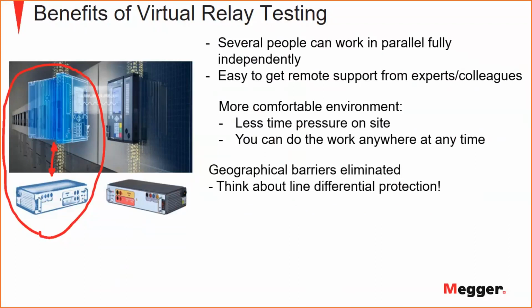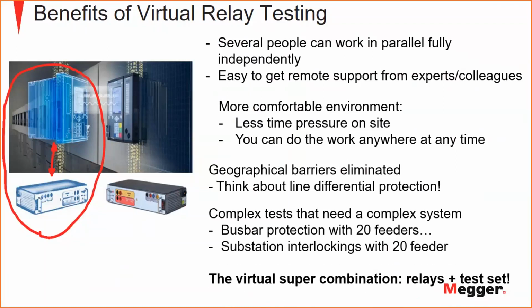Think that you can have two digital twins connected, and now I'm talking for Siemens, so I apologize if I say something wrong, but I believe it is possible to have two line differential protection relays, connected to the digital twins, connected to the real multiplexers into a communication channel. I guess, I'm not promising that. Anyway, I know you can connect these two relays together in the virtual world and test the line differential protection without doing the test we talked about yesterday, in the presentation of yesterday. This test can still be done in the substation, of course, but instead of performing hundreds of tests, you perform only 2 or 3, because the others you have already done in the virtual.